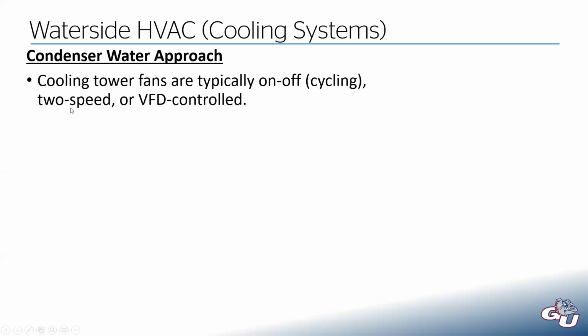Or commonly they're two-speed fans. You can have a low speed and a high speed. So maybe you can run at low speed for a while, but then once you start to get out of set point, you bump it to high speed until it's under control, and then you bump back to low speed. So that would give you much less fluctuations around your set point. Or the best option would be to control it with a VFD and actually control the fan speed to whatever you need. So if you only need 70%, then you run that fan at 70% fan speed.